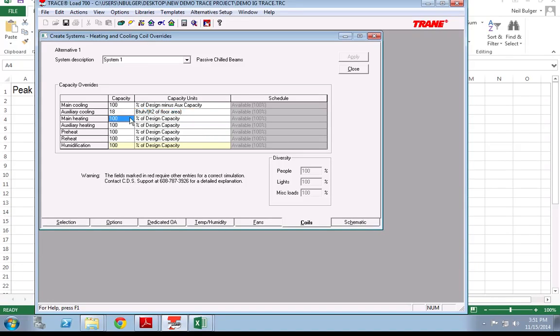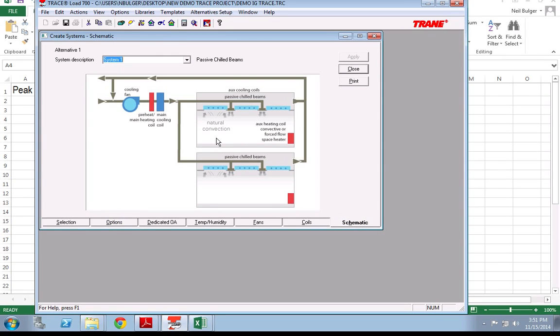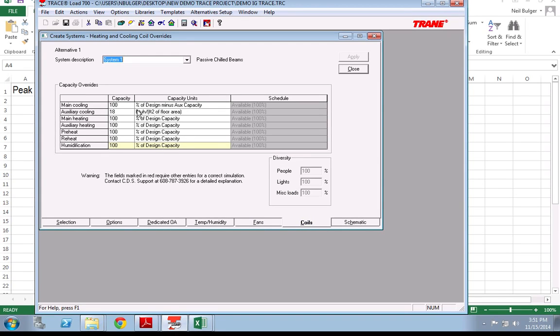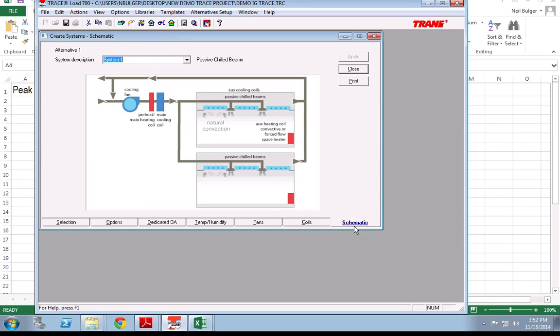So what's now going to happen is this is going to go first. And this is going to say, figure out how much cooling each room needs. And if it's below 18, then the fresh air will just be sized based on fresh air. And there will be no cooling oversizing. Yet now, when it sizes the whole system, there may be some rooms that don't hit their 18 cooling load capacity, and that's fine. Those zones won't contribute to oversizing the main air handling unit.